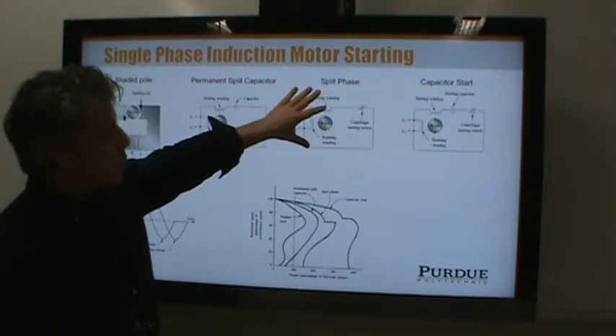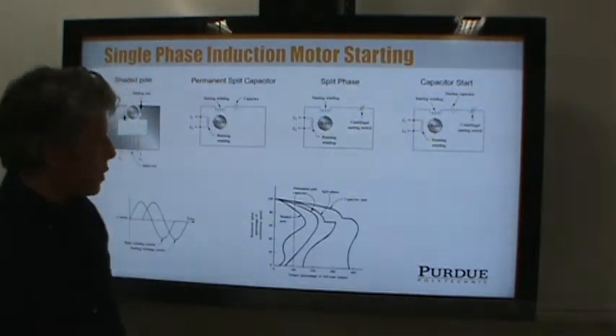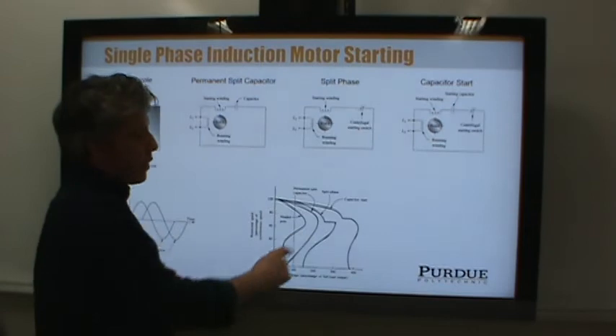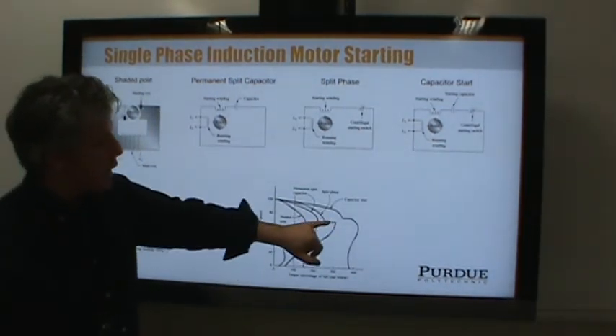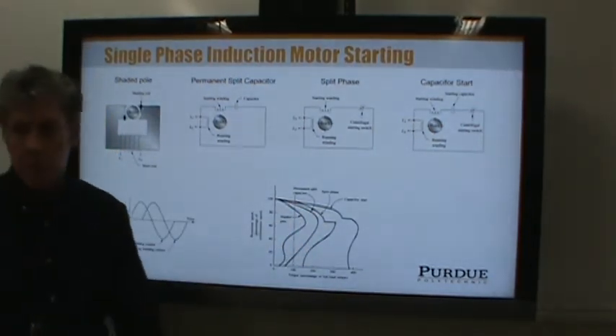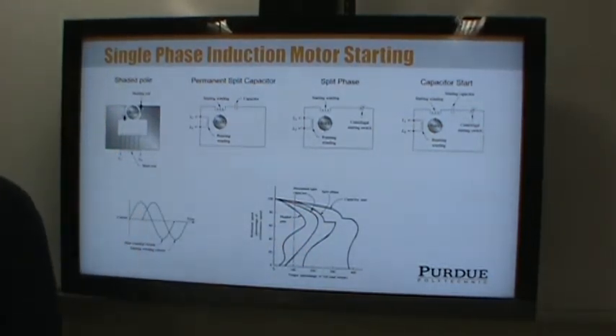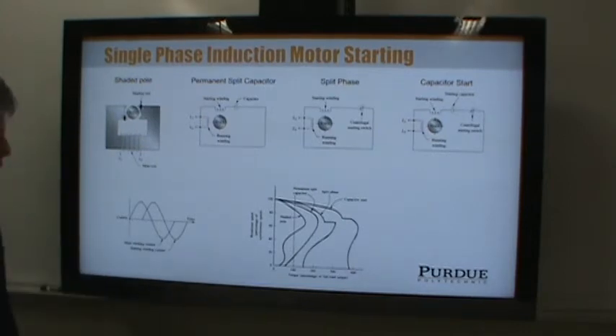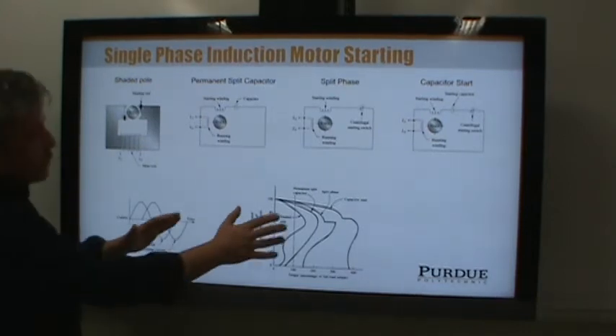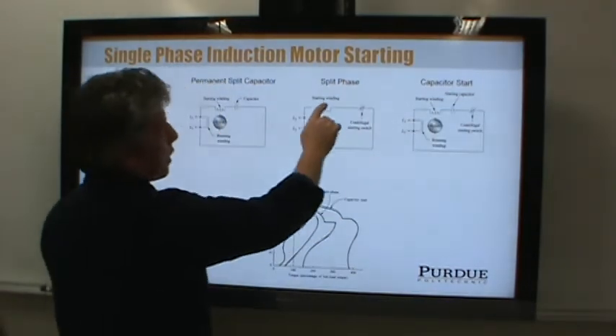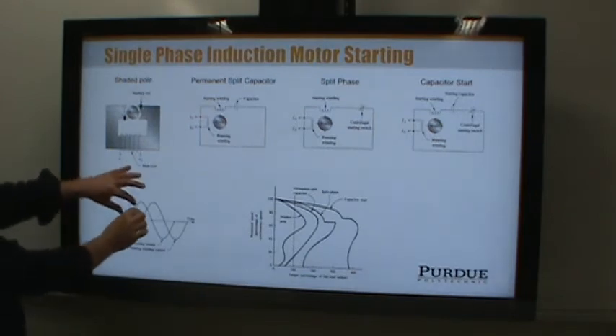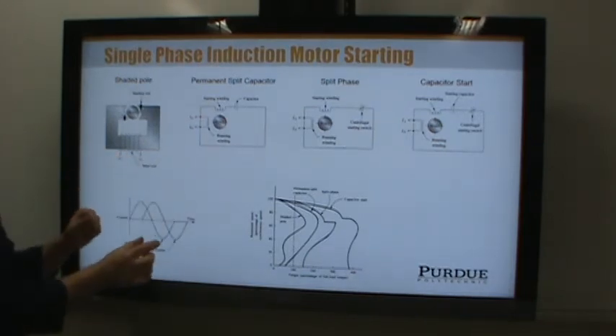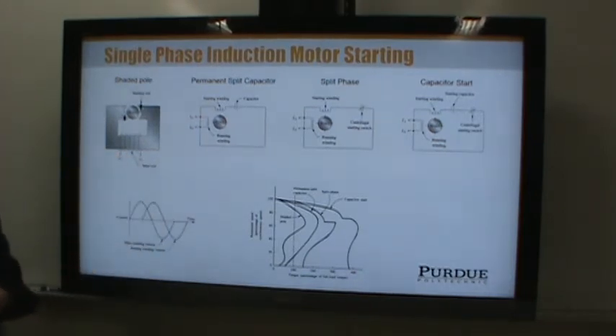There's also a split-phase motor that includes a centrifugal starting switch but no capacitor. Once the extra phase is cut out, the main winding operates. What all these approaches — capacitor start, split phase, or permanent split capacitor — really do is create an offset phase between the two coils, and with an offset phase you can generate torque in the motor to actually get it to turn.